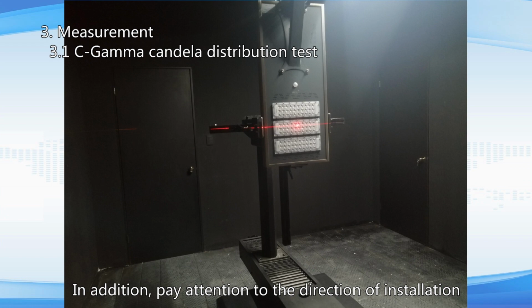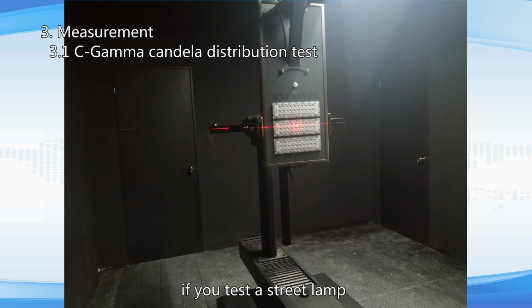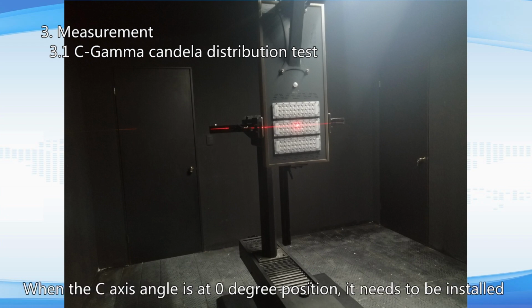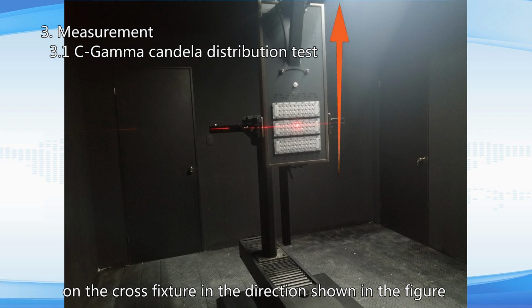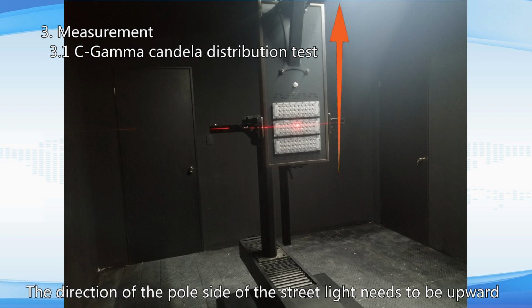In addition, pay attention to the direction of installation if you test a street lamp. When the C-axis angle is at 0 degree position, it needs to be installed on the cross fixture in the direction shown in the figure. The direction of the pole side of the street light needs to be upward. And select roadway here. The other steps are the same.